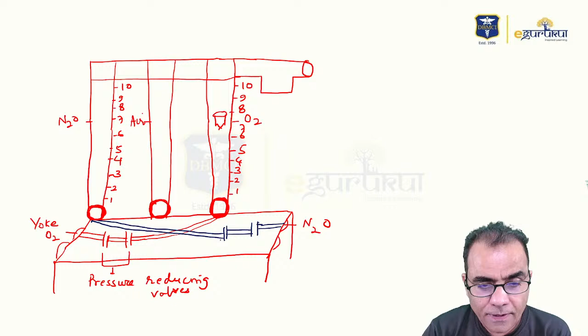Now, these, I told you, are glass tubes, transparent tubes, but still you cannot see the gas flowing through them. You cannot see a gas, but we have to be sure that gases are flowing. Not only flowing, we have to set the flow rates. So for that, they have devised an aluminum structure inside each of these tubes, which is called a bobbin. Now, how does this bobbin work? In its upper rounded part, there are cuts.